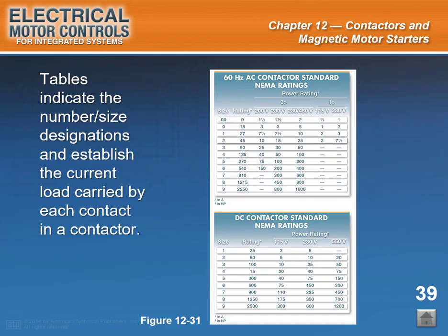Start of slide 39. Slide caption: Tables indicate the number/size designations and establish the current load carried by each contact in a contactor. See Figure 12-31. Magnetic contactors, like manual contactors, are rated according to the size and type of load by the National Electrical Manufacturers Association, known as NEMA. Tables are used to indicate the number/size designations and establish the current load carried by each contact in a contactor. The rating is for each contact individually, not for the entire contactor. For example, a size 0, 3-pole contactor rated at 18 amps is capable of, and rated for, switching 3 separate 18 amp loads simultaneously. End of slide 39.